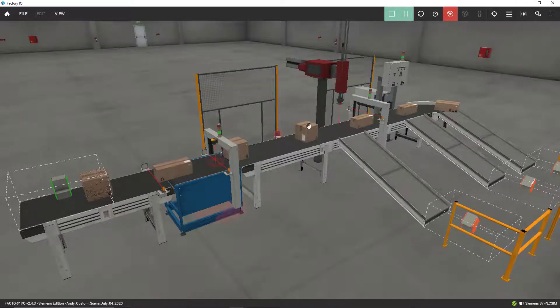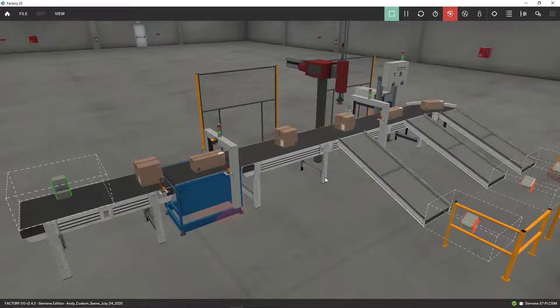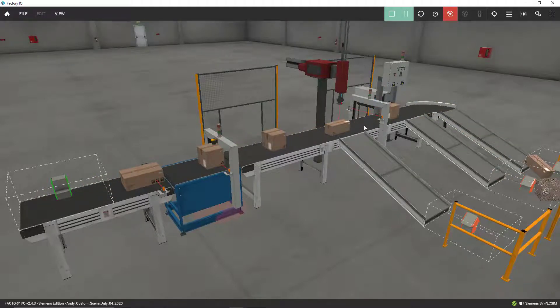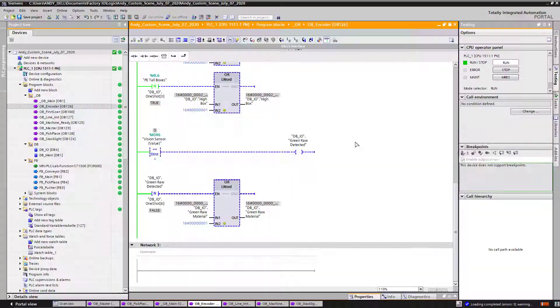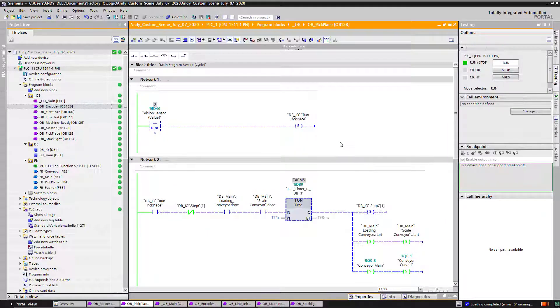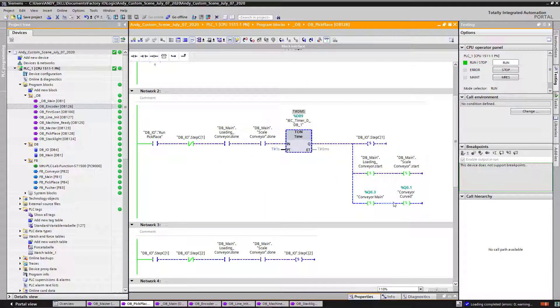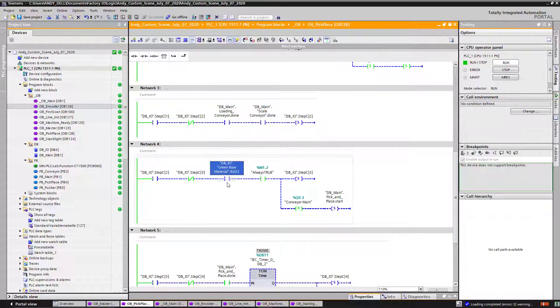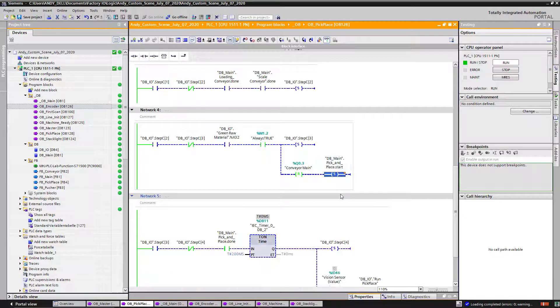The pusher right over here — when you see a large box it activates. My conveyor is pretty long, about six meters, so I have to keep track of my shift register word. When bit number 32 activates, that's on my pick and place subroutine — I look for that bit, and once my conveyors and everything are activated, I get my done bit for my function blocks. When bit 32 activates, that's when I start my pick and place subroutine.